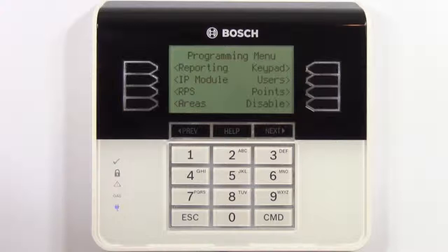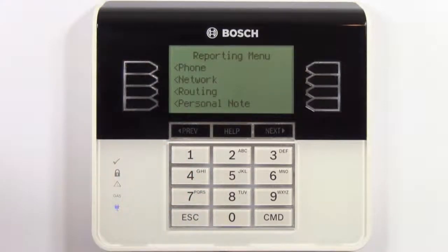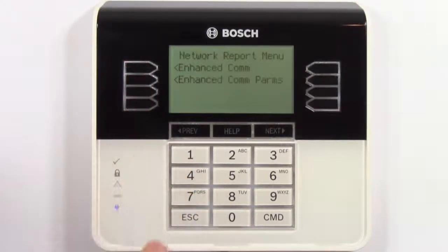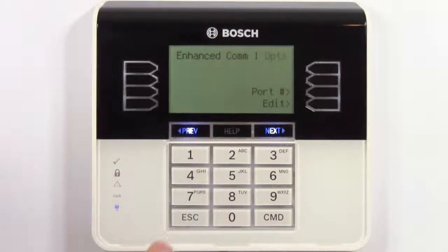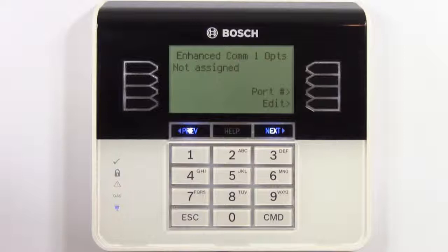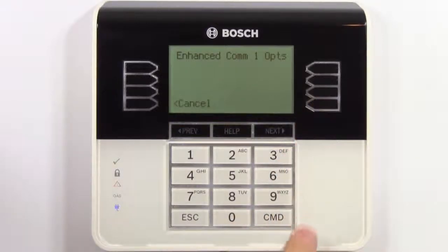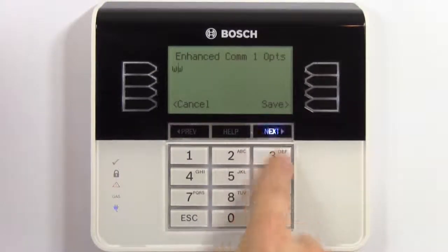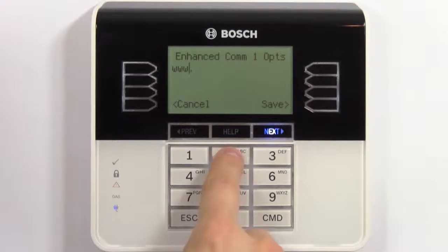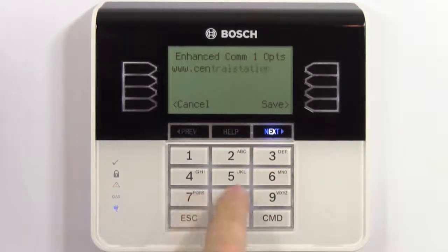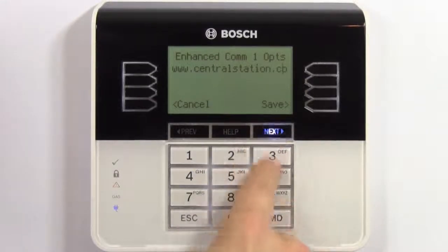First, we'll need to configure how the panel will report to the central station over the network. Select reporting and enter the enhanced communication parameters menu. Press edit to enter either the DNS name or the IP address of the central station receiver. In this video, we'll enter a DNS name. When you finish, press save.